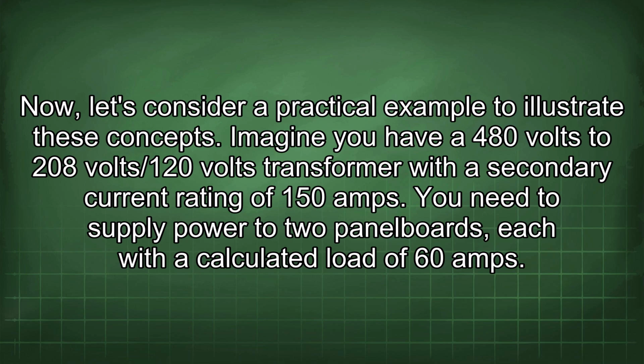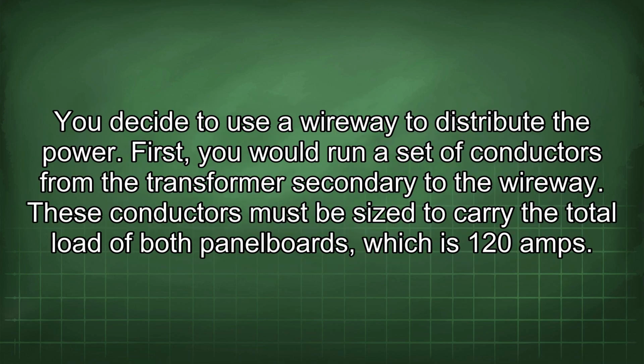Imagine you have a 480 volts to 208 volts / 120 volts transformer with a secondary current rating of 150 amps. You need to supply power to two panel boards, each with a calculated load of 60 amps. You decide to use a wireway to distribute the power. First, you would run a set of conductors from the transformer secondary to the wireway. These conductors must be sized to carry the total load of both panel boards, which is 120 amps.